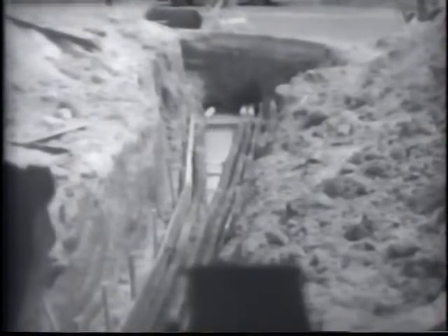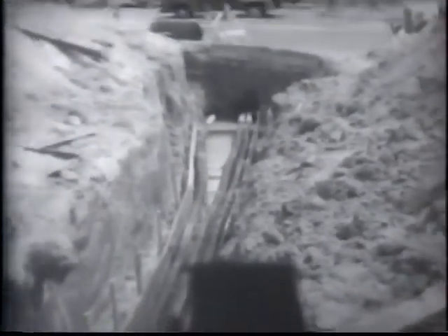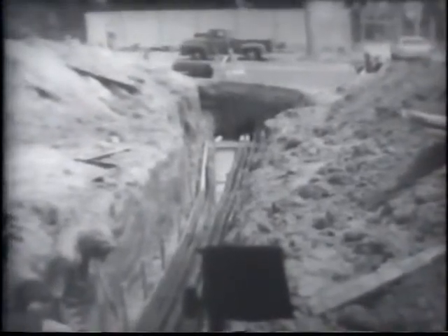This was one of those places where we were talking about where we augered a hole underneath the street. This happened to be a state highway up here, and as you can see, they started out on the other side. The hole was augered from the other side of the street over to here, and they started out about 3 foot apart. These two came out pretty good, but this one wound up hugging the other one over there. That's the one thing you run into when you auger underneath streets.